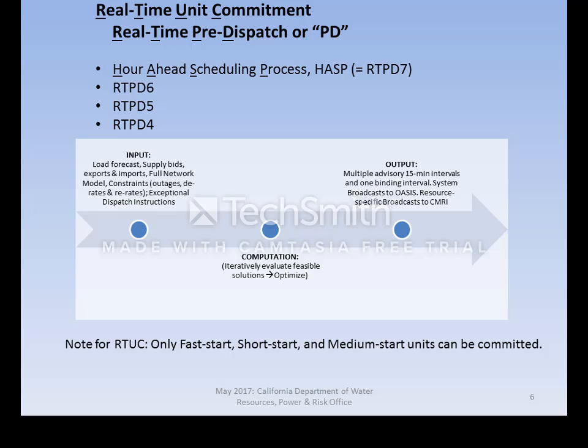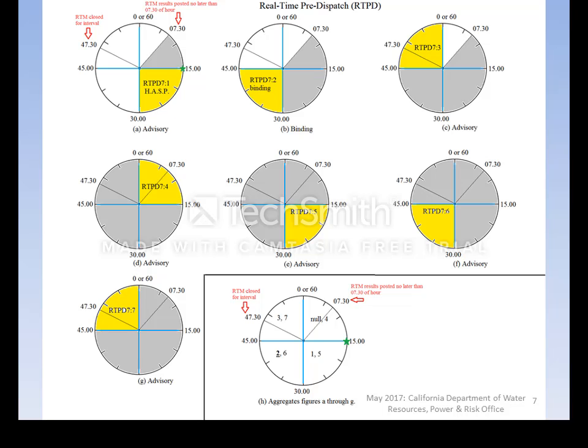This is analogous to the example where units were committed and decommitted to follow demand of the load profile curve. With the predispatch applications, those inputs along with the network model are utilized to identify feasible solutions. The predispatch application selects the most optimized feasible solution, which contains a table of unit commitments. This table is the basis for unit commitment instructions — one binding and multiple advisory — transmitted to individual generation units via the Automated Dispatch System (ADS). Note that since the optimization timeline is at most 105 minutes, only certain generation unit types may be committed by PD applications.